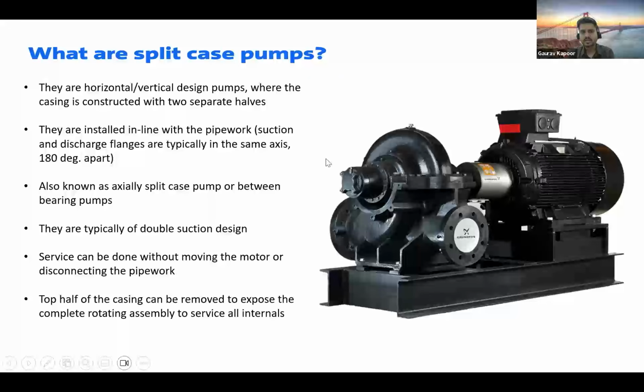Because as the name suggests, split case, the casing opens and splits into two halves, either horizontally or vertically. It means if you open these bolts, as you can see, the top half will come up and the bottom half will stay in the piping itself. So you do not need to touch the piping, only the casing comes apart, and once the half of the casing opens, you can access all the mechanical seal, bearing, shaft, impeller, everything can be visually checked, and if it needs to be repaired or replaced, it can be replaced.